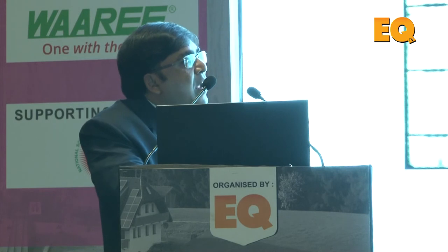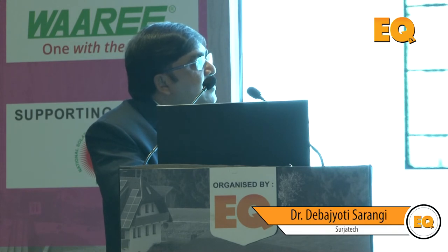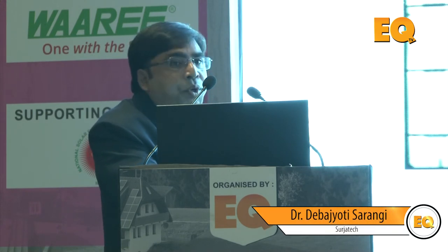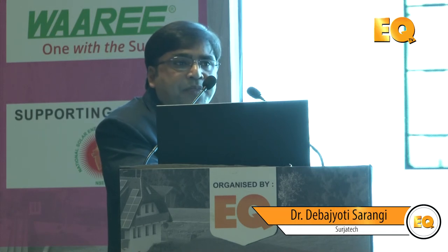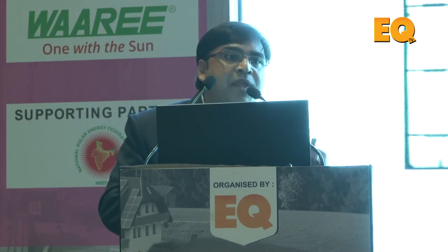Why is it really happening? You can see that with time, this EVA will generate the acetic acid. And this acetic acid really corrodes the contacts. You're losing the power. So the message is that you really need to understand the module degradations, one of them. And I'm really very sorry to say that the module manufacturers are spending $72 for the solar cells of a 72-cell module, and they are not really ready to spend more than $3 on the encapsulant. And that is on top of the solar cells, really contributing this acetic acid and degrading the modules.